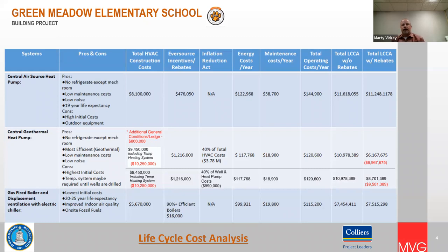If we do go with the gas-fired system, we need provisions in there for the changeover to electric in the future. Maybe you retain gas for peak shaving or something like that. We could see that. In other cases, we've had electric resistance backup — a good example is a couple weeks ago during that extremely cold stretch, air source heat pumps in some cases were struggling, so they'd use electric resistance as additional spare or backup capacity in the coldest temperatures.